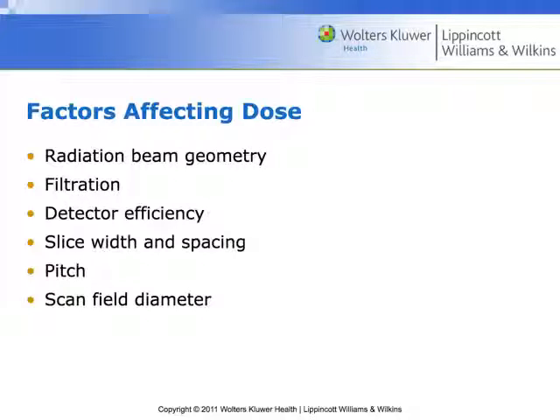The scan field diameter also plays a part — not the display field diameter, which only affects spatial resolution of computed pixels, but the actual scan field diameter. We have very little control over it; it's hard-set in the machine. But as the scan field gets bigger, we're exposing a bigger area and will have increased dose.